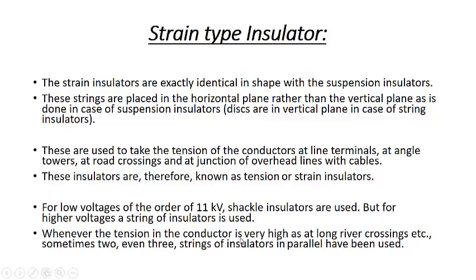Whenever the tension in the conductor is very high, at a long river crossing, etc., sometimes two, even three strings of insulator in parallel are to be used. So when this tension is more, we can use this string type of insulators in parallel to each other so that they share this type of load or this type of tension.